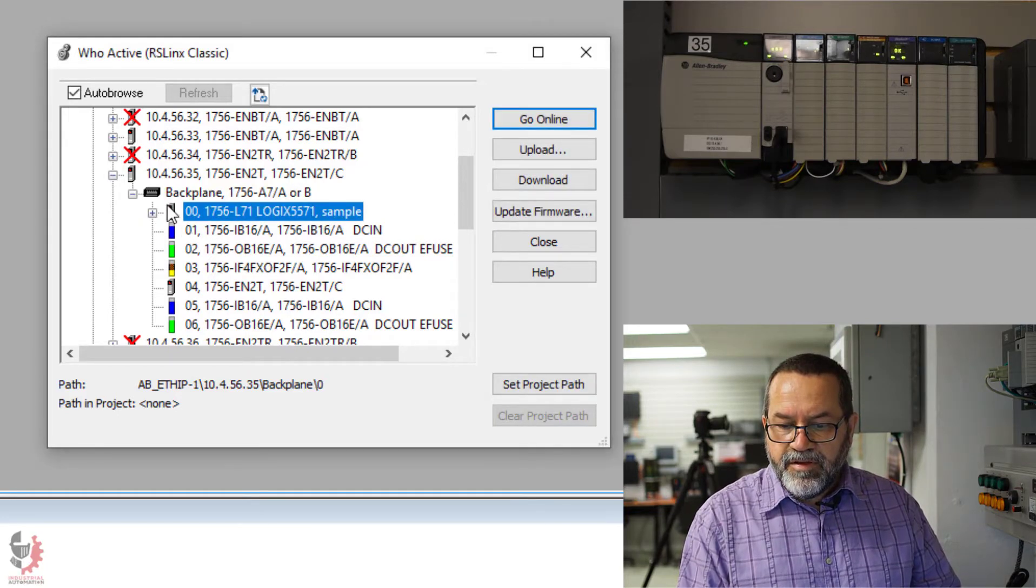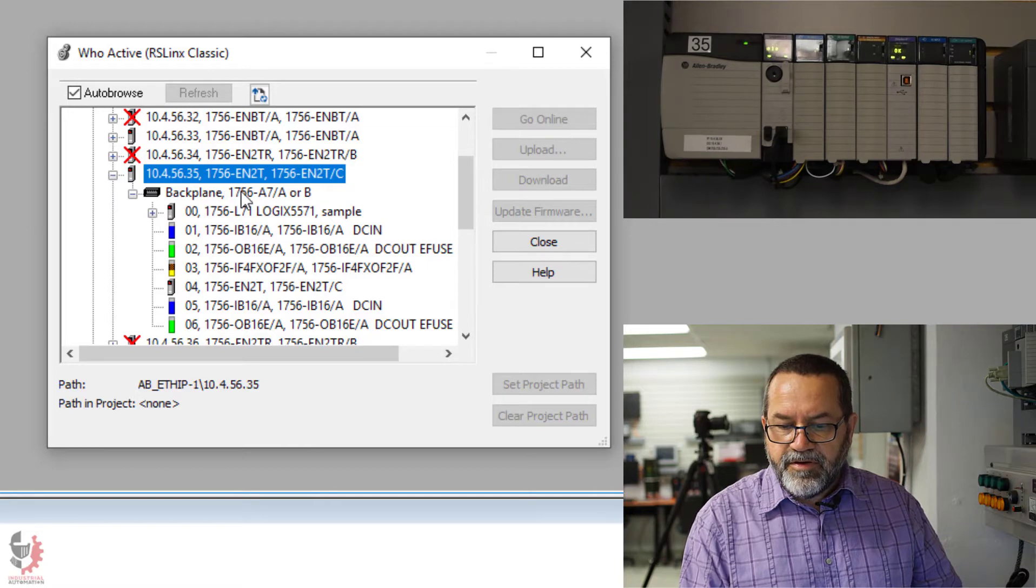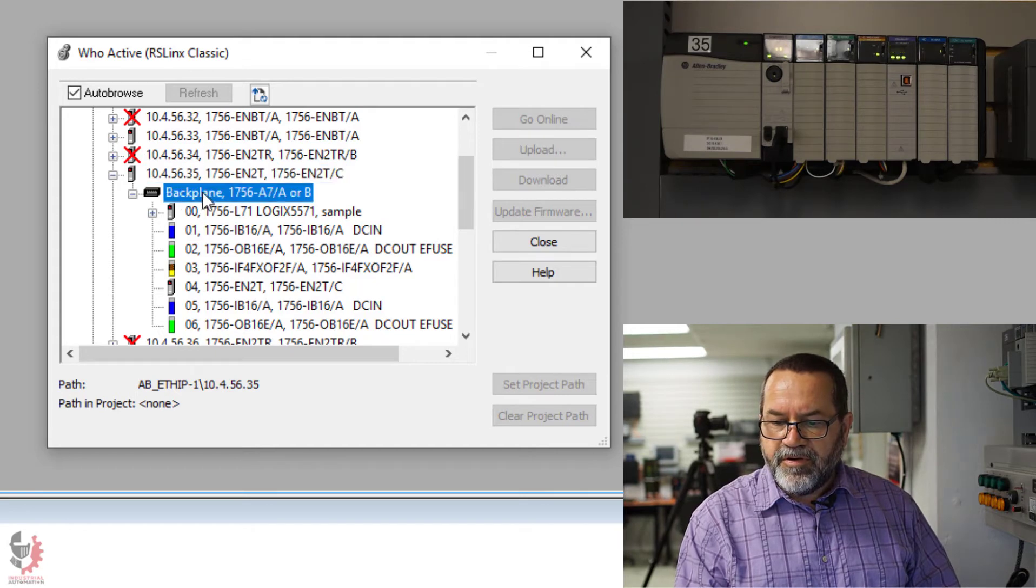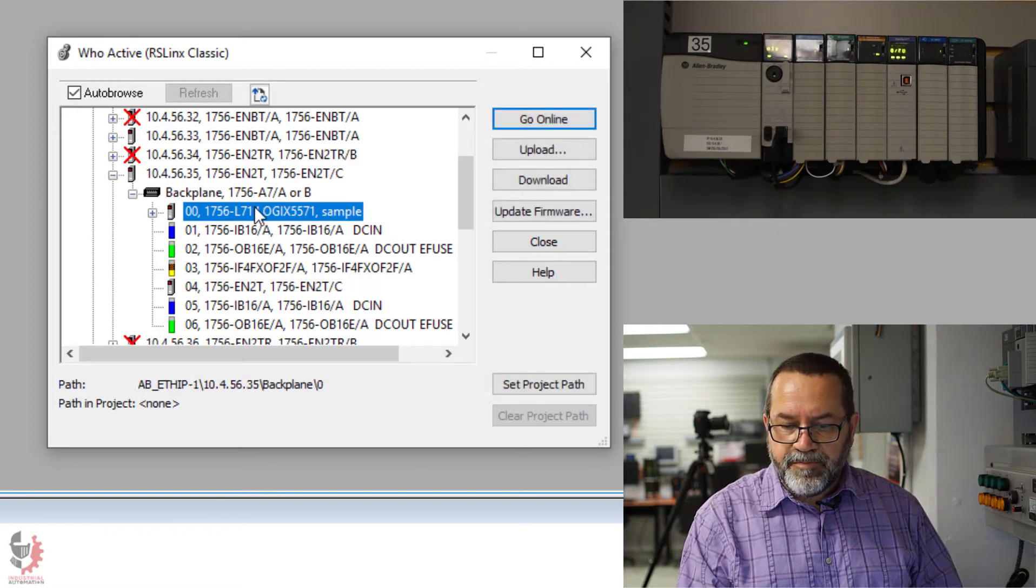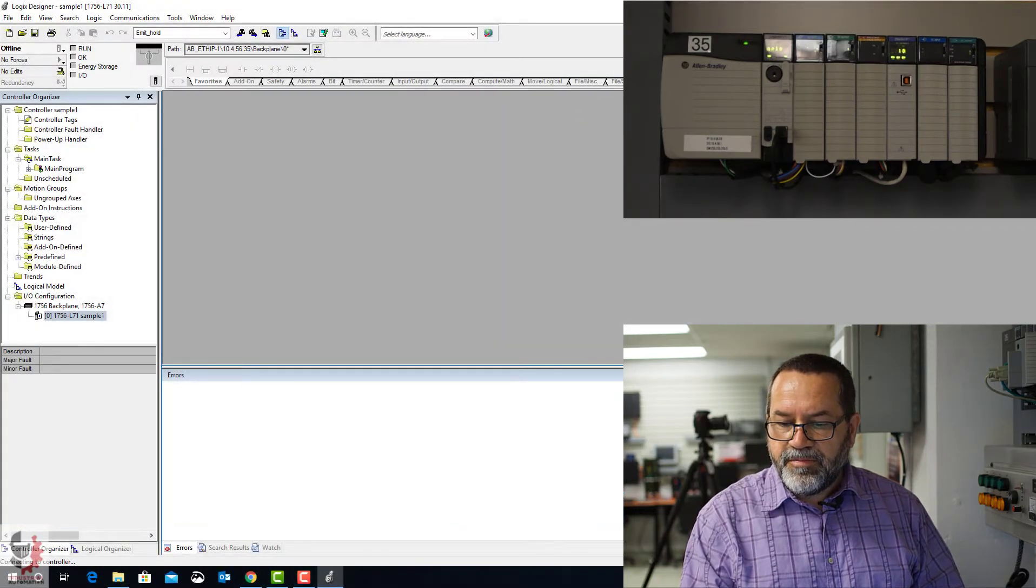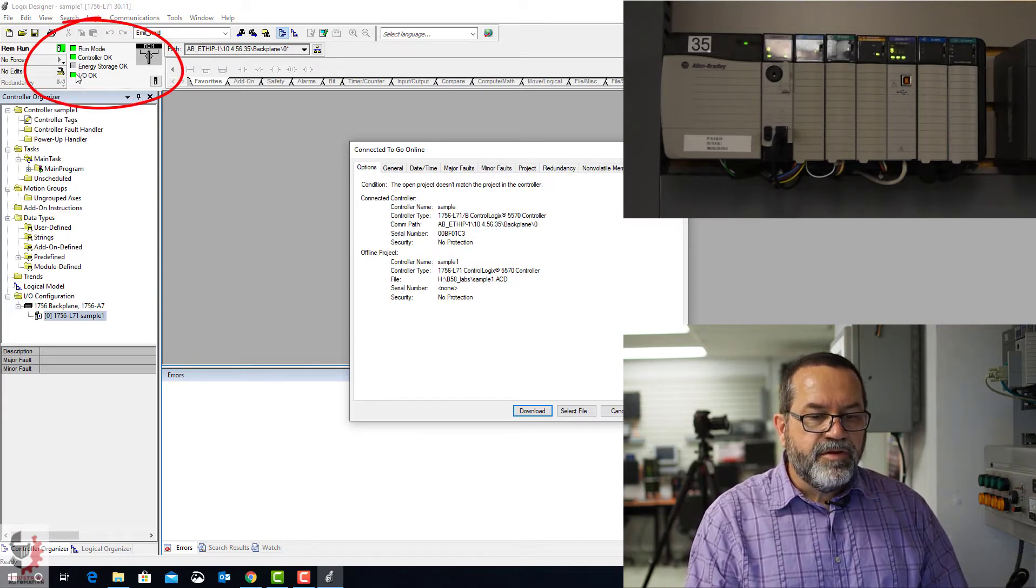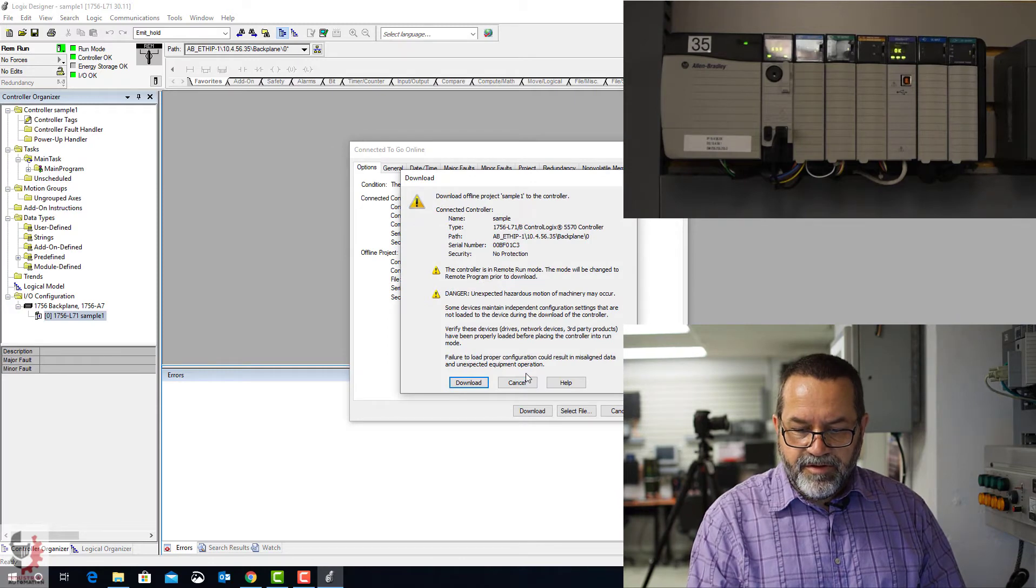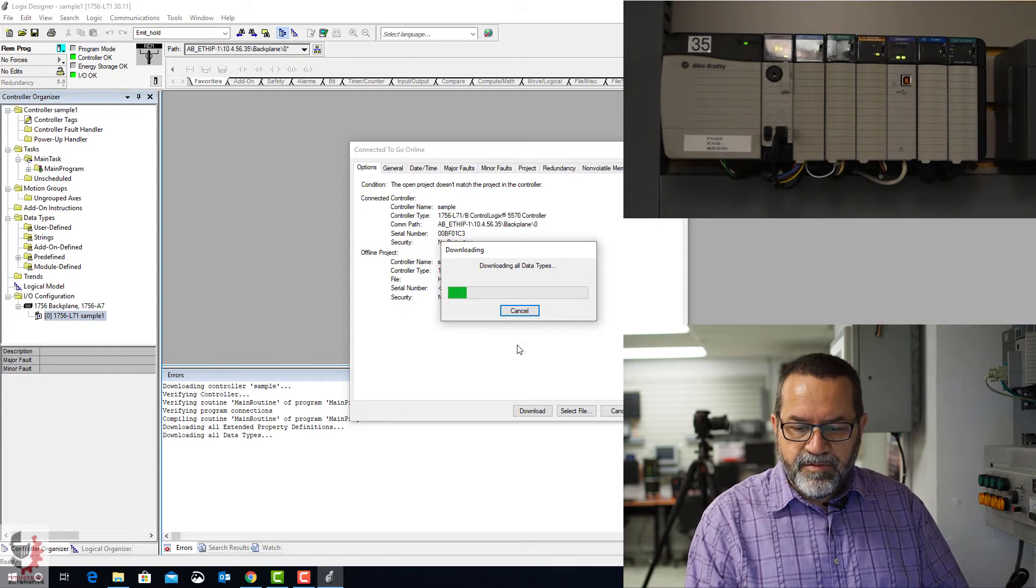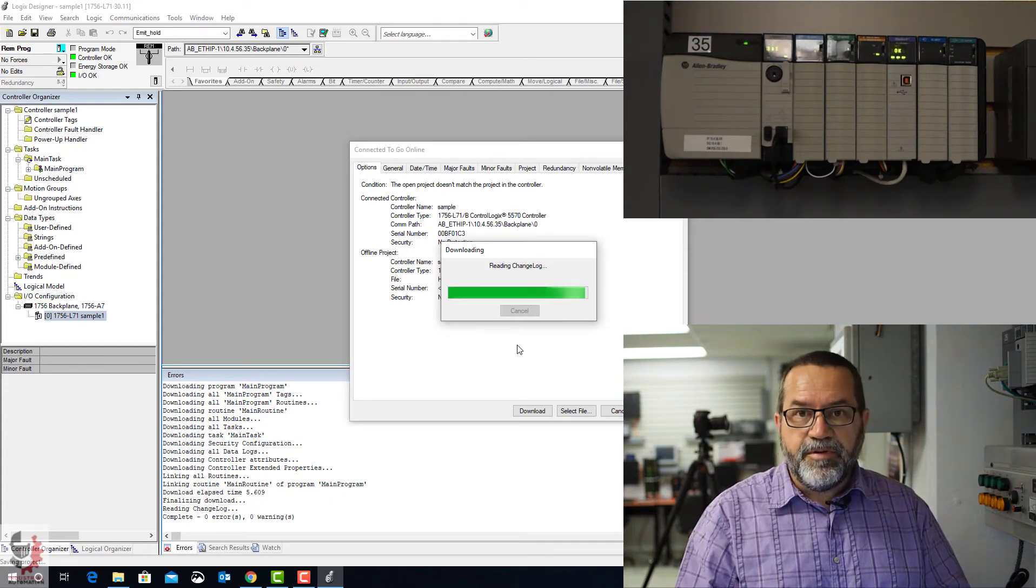So I'll click on the controller. Notice if I'm clicked on the backplane, I can't go online. If I click on the communication card, I don't have the option to go online or upload. Same with the backplane, because I can't talk to a backplane. But when I click on the controller, now I have the options. So click on the controller, and now I'm going to go online. Okay, when I do this, notice these green lights here. Right now I've got two green, a gray, and then another green for IOK. But let me download, because I'm not fully communicating with this controller yet. Now what I'm doing is I'm downloading what's in Studio 5000 to that PLC, to the PLC controller.